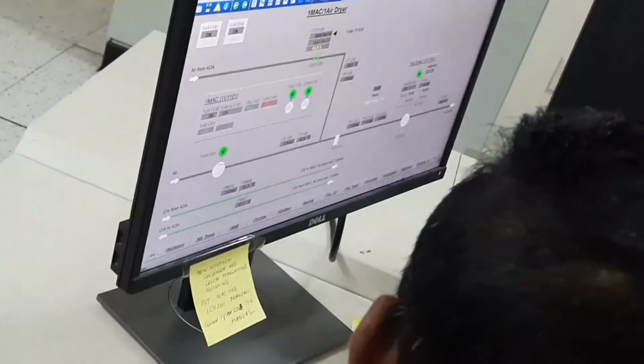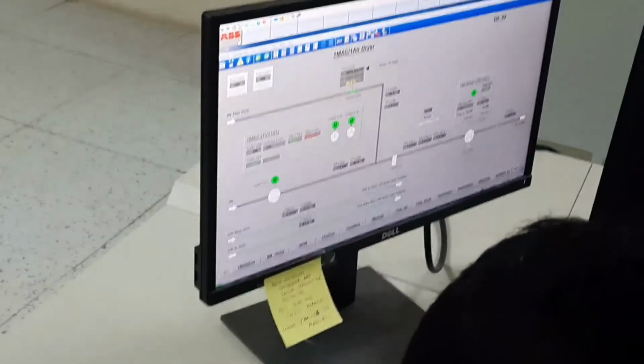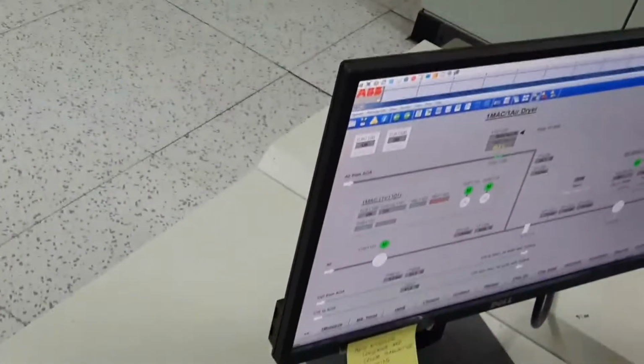So now our consumption is less. We are producing only 1,000 normal meter cube nitrogen. If we produce 1,300 normal meter cube nitrogen, the air flow required is 3,700. But we are producing less, only 1,000. For that reason, this air flow is also only 3,000.